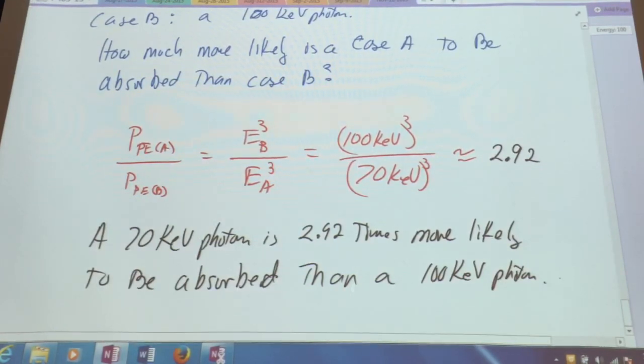So is that your experience? Higher the kVp, what happens to the image as you raise the kVp, changing nothing else? What happens to your pictures? Well, suppose you just do the same object and you just do it with higher and higher energy. What do you think might happen? Less contrast. Yeah, you're just punching the photons right through the object, you're going to get less contrast.